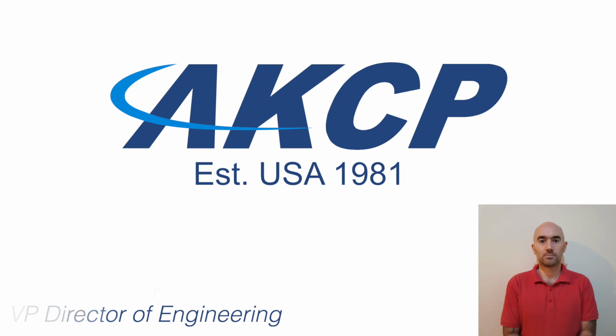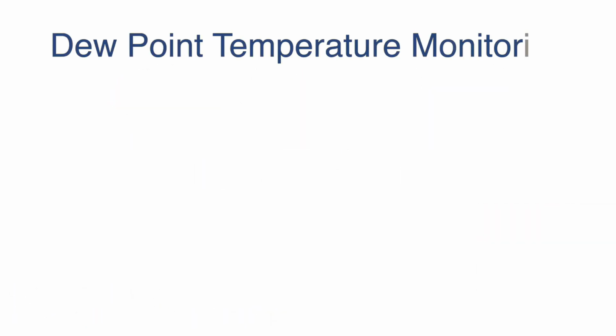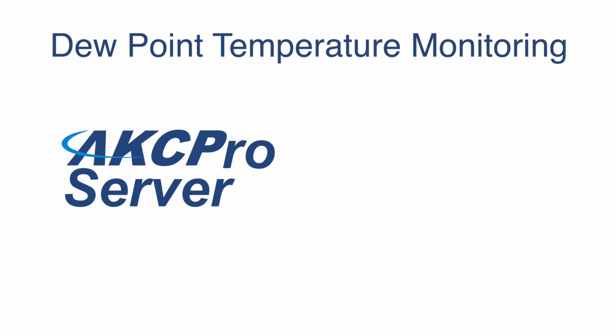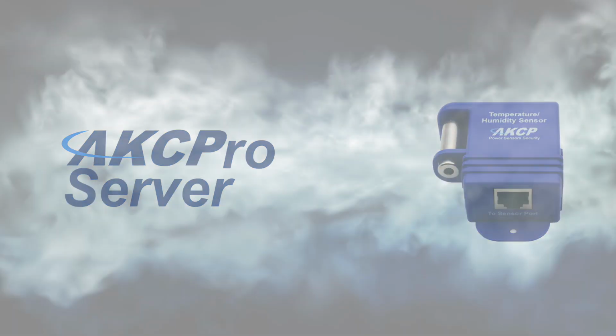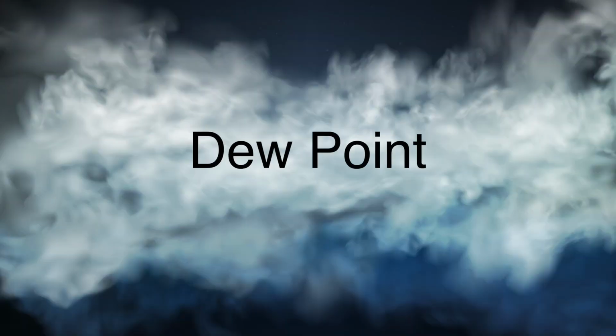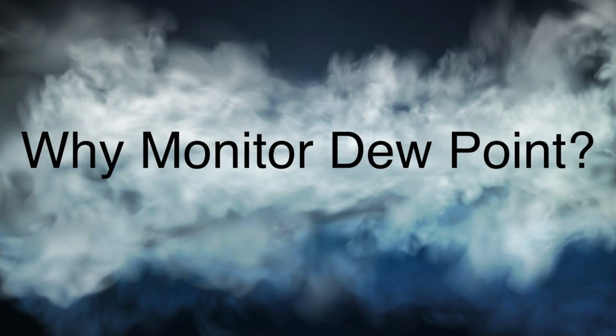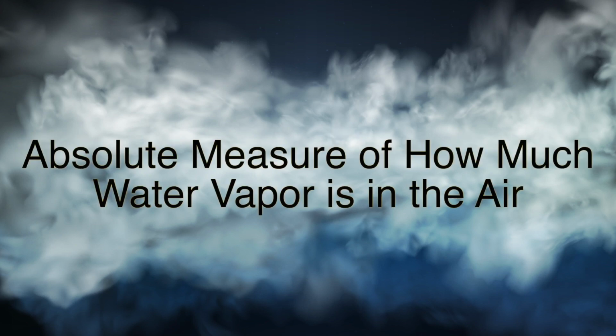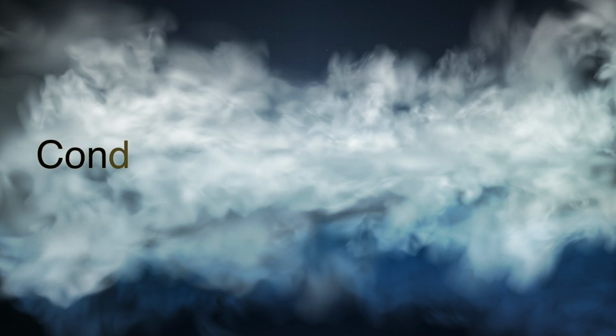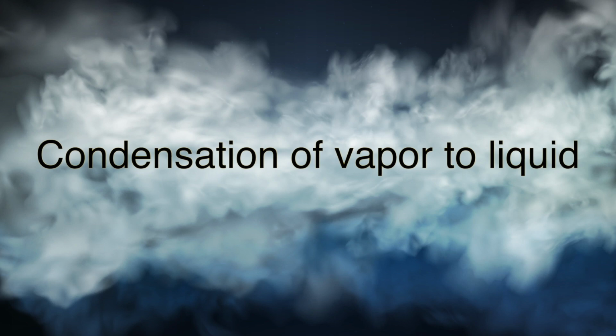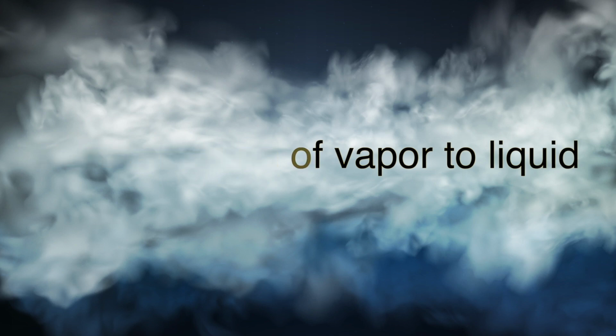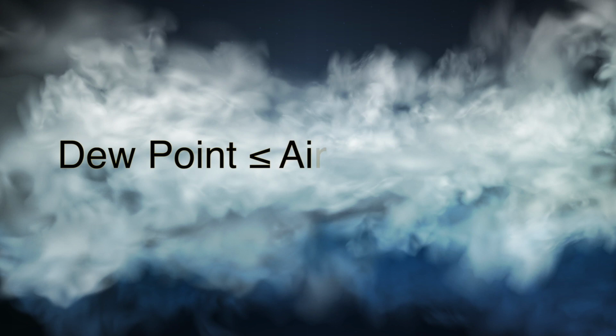Welcome to this short video on how to monitor the dew point temperature with the AKCPro Server and AKCP temperature and humidity sensors. First, let's talk about the dew point temperature. What is it and why should it be monitored? Well, the dew point temperature is an absolute measure of how much water vapor is in the air. It is the temperature at which the air can no longer hold water vapor within it, and therefore some of the vapor has to condensate into liquid.